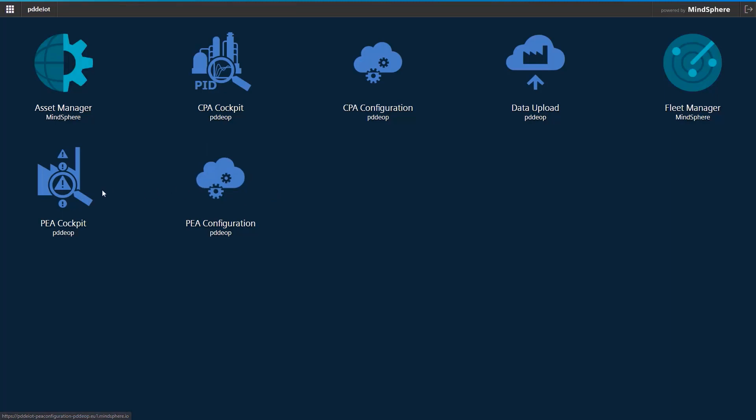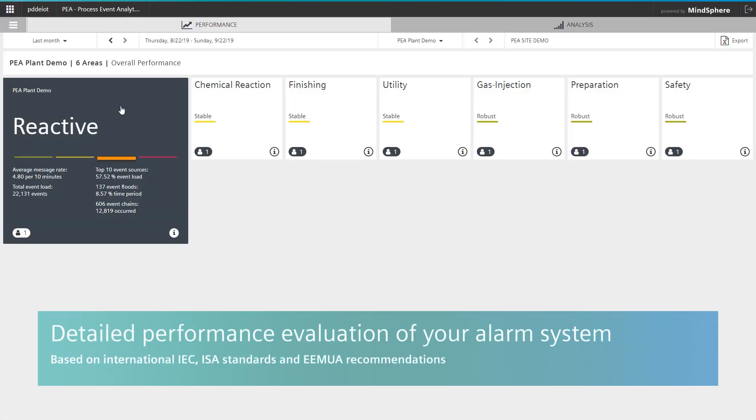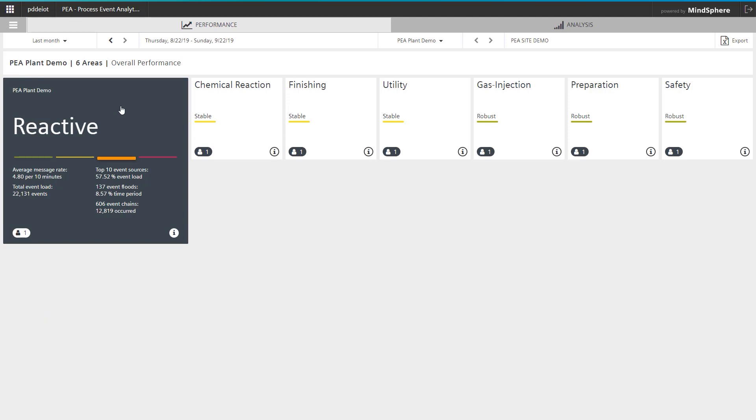The Process Event Analytics Cockpit provides a granular evaluation of the performance of your alarm system. This evaluation is based on international IEC and ISA standards, as well as the recommendations of EEMUA 191 3rd edition. For the selected time range from August 22nd to September 22nd, the overall status of this demo system was evaluated as reactive.